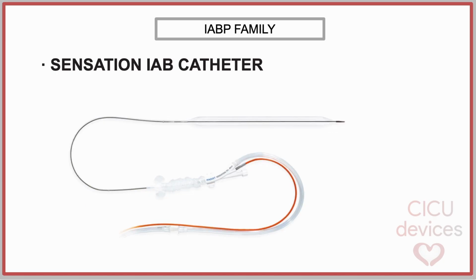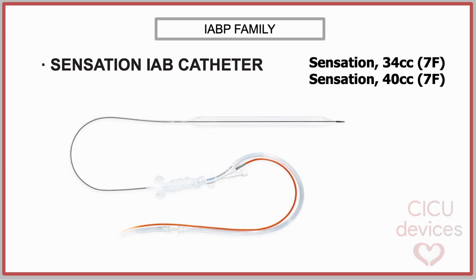The Sensation IABP catheter is Getinge's premium fiber-optic intra-aortic balloon catheter, specifically designed to combine a low-profile shaft with advanced hemodynamic monitoring. Its most distinctive feature is the incorporation of an integrated fiber-optic pressure sensor located at the catheter tip, enabling direct measurement of central aortic pressure without the limitations of conventional fluid-filled systems. The Sensation catheter is available in 2 balloon volumes: a 34 milliliters model recommended for patients shorter than 162 centimeters, and a 40 milliliters model for patients taller than 162 centimeters. Both catheters have an external diameter of only 7 French, making them the smallest IABP catheters in the Getinge portfolio.